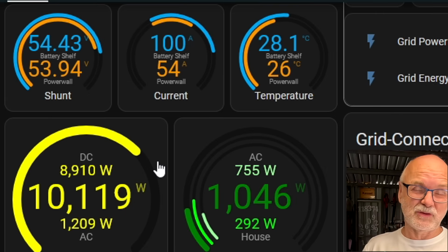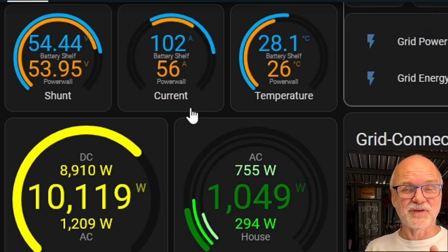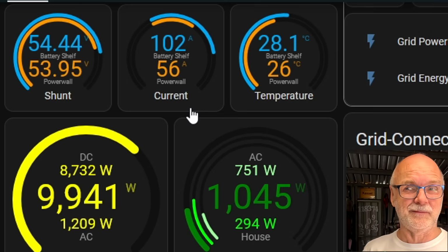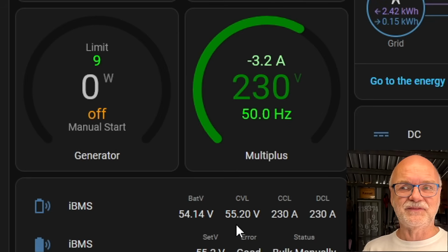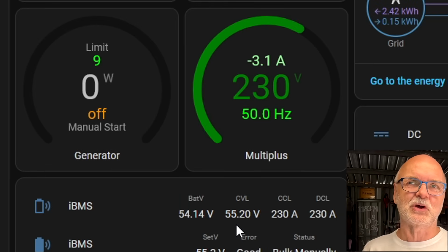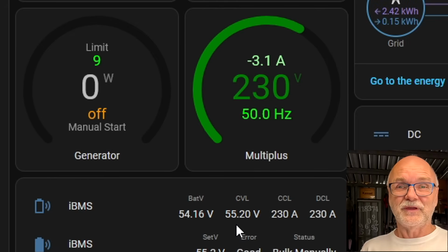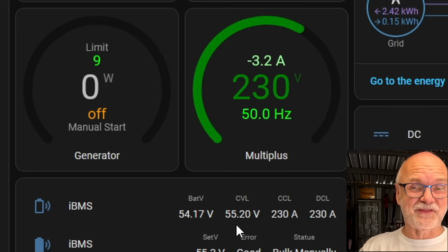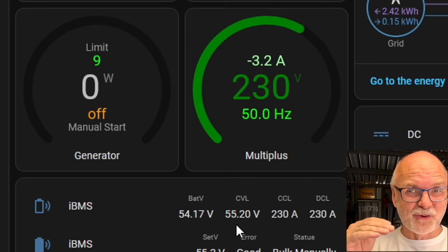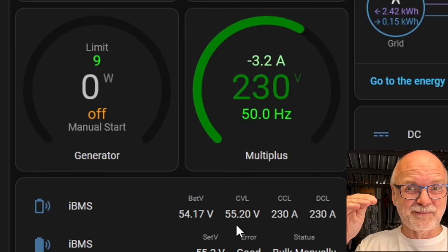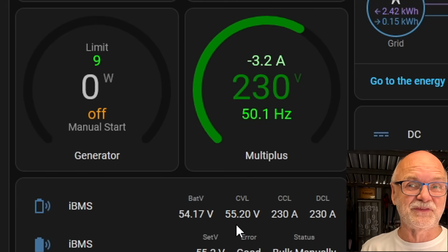Then if we turn on a big load, like charging the vehicle, and the current into the Powerwall batteries goes under 50 amps, I actually increase the CVL again, but only by 0.01 volts, 10 millivolts every 20 seconds. So increasing goes in 10 millivolt increments, but decreasing goes in 100 millivolt increments. This is because if I go over 63 amps, I want to react fast and reduce the current, but to increase it again I'm really cautious, going step by step to see if it makes a difference and if we come close to 60 amps again.